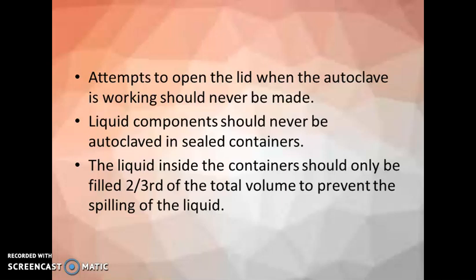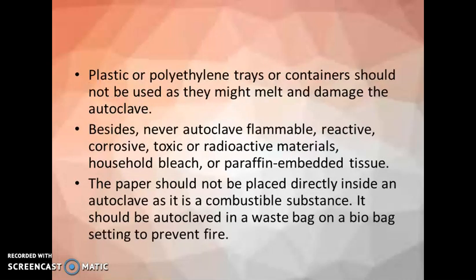Then the next point, liquid components should never be autoclaved in sealed containers because it doesn't ensure proper sterilization. The liquid inside the containers should only be filled to 2/3 of the total volume to prevent spilling of the fluid. Then plastic or polyethylene trays or containers should not be used because they might melt and damage the autoclave. So don't use plastic or polyethylene trays. Besides, never autoclave flammable, reactive, corrosive, toxic or radioactive materials, as well as household bleach or paraffin embedded tissues. So we should not autoclave these types of items.